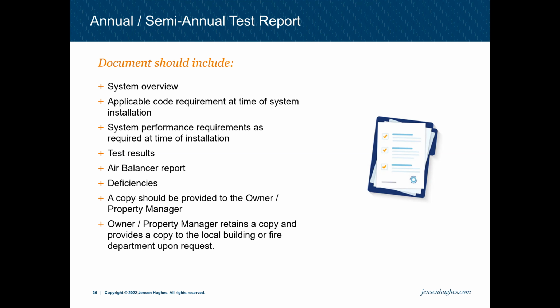These test reports should include a system overview, the applicable code and requirements at the time of the system, and the design requirements and intent of the system, so what pressure differentials or CFM was required. These reports should also include the deficiencies, that is, items that need to be addressed. For example, if the door opening force is too high, the door doesn't latch, fans don't turn on, etc. And then the property owner or property management company must maintain a copy of these reports and be able to provide them to the local building or fire department upon request.